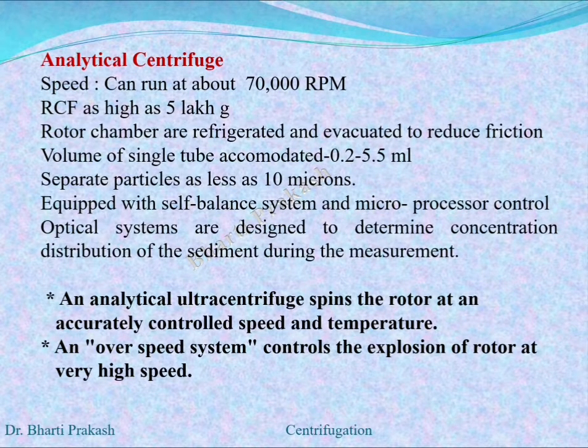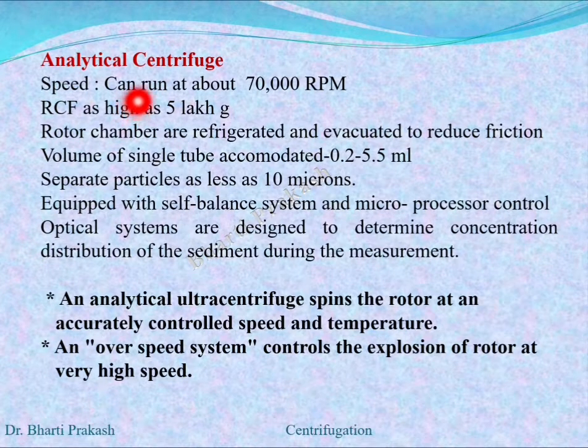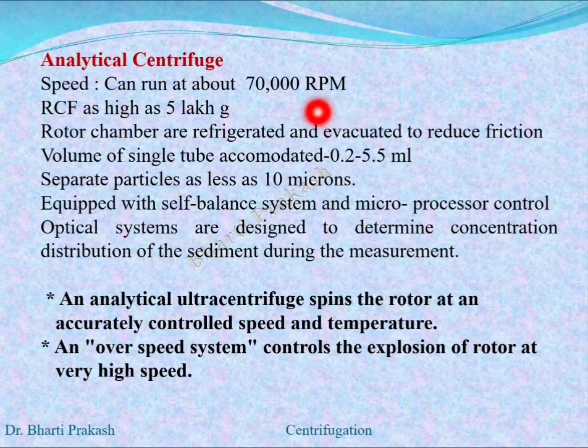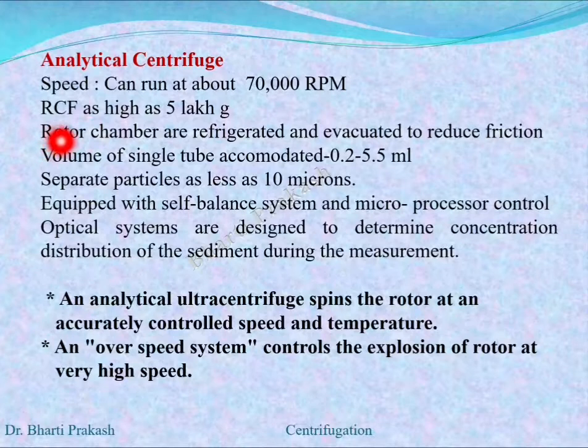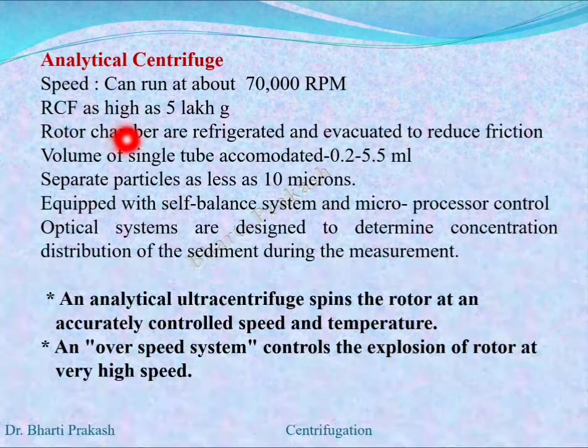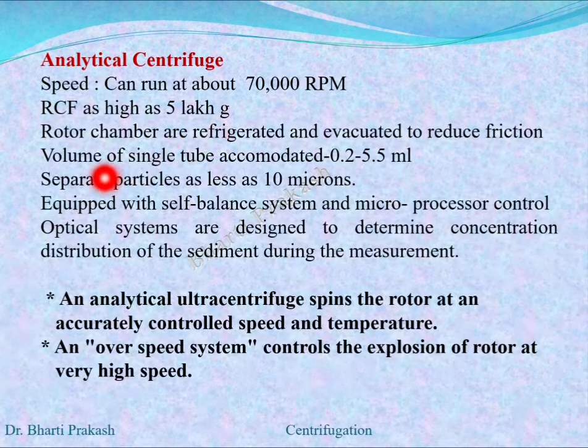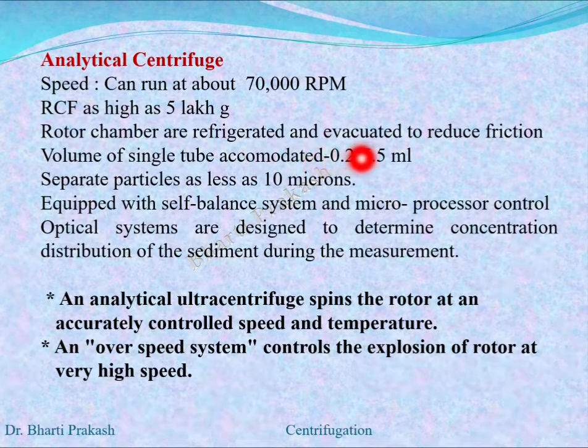Now let us study the features of the analytical centrifuge. First, the speed — it can run at about 70,000 rpm. The relative centrifugal force, or RCF, is as high as five lakh times gravity. The rotor chambers are refrigerated and evacuated to reduce friction.